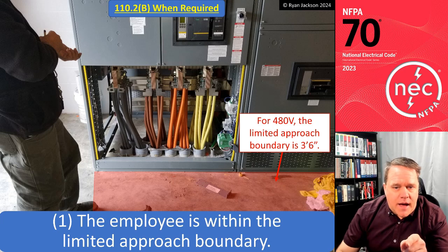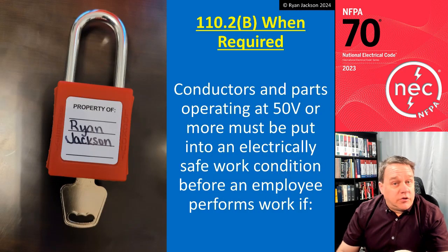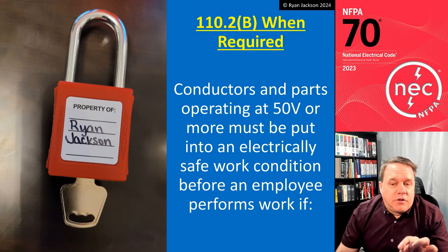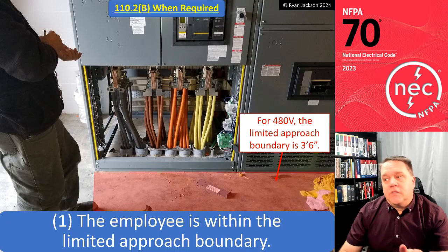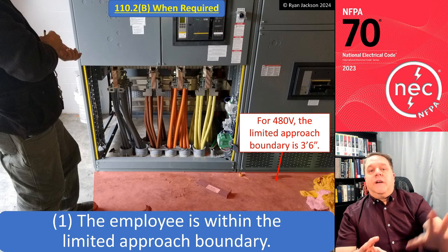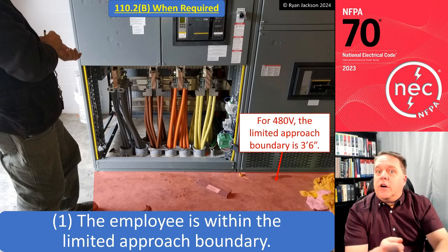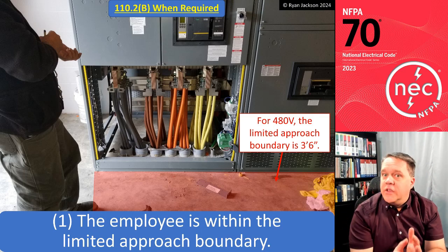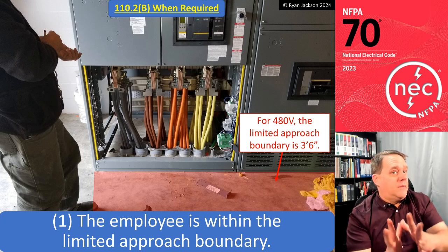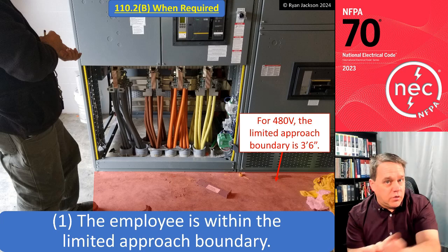And if we go back, it says what? Conductors and parts above 50 volts have to be put into an electrically safe work condition. Now that means that it's shut off and it's tagged out and it's measured to verify the absence of voltage and some of the other steps, right? So it's not just a matter of shutting it off. It's going through the whole process.